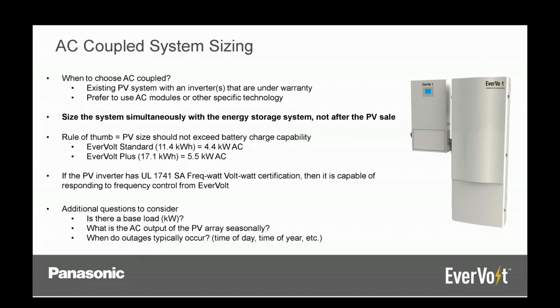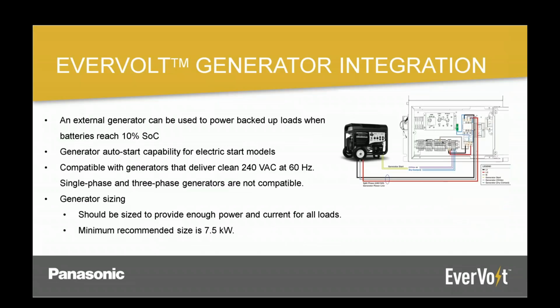Before, I mentioned you want to design for the worst case, so that would be your peak output of the year. But it makes sense in a lot of cases to look at whether this is really going to be a problem. If there's going to be too much PV for one month out of the year, potentially on very bright sunny days, you can use your judgment on that design. And then again, when do outages typically occur? If you know that your outages are typically during the summer months or the winter months, or different seasons or different times of the day, you can size your PV array to handle that. Again, this is more advanced sizing consideration, but the basics are above. So if you're using a newer inverter, you generally can oversize the PV array.